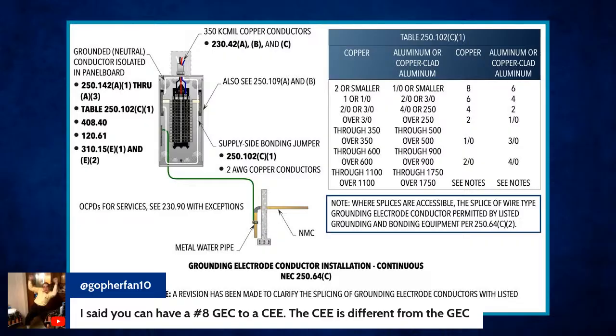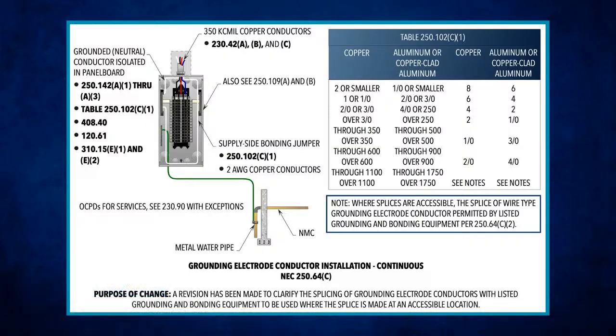All right. Then number 4, they say you can have bolted, riveted, or welded connections. Of course, that's to your structural metal frames. Or you can have where you have threaded, it can be welded, soldered, or they like to have a term they refer to called brazed. Or you can have a bolted flange connection. Of course, that's to your metal water pipe. Okay. So they allow you to do those types of connections too. And what we also did here is to tie this in with table 250.102(C) based on these sizes.